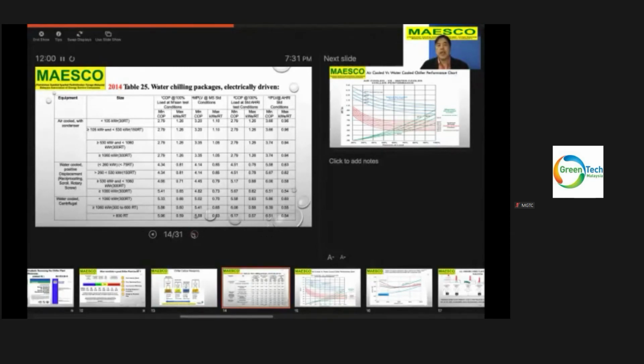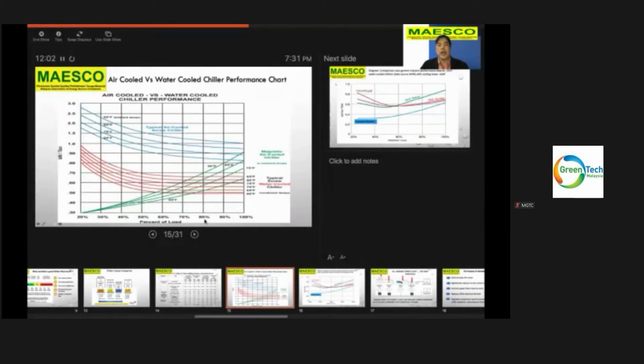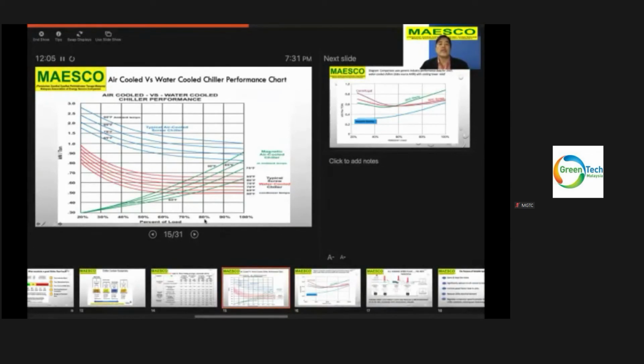Now let's look at the other one, air-cooled versus water-cooled chiller performance charts. You must know all these charts, because if you select the wrong chiller for a wrong application, it's like a baby. The life cycle of the chiller is roughly 20 years. And if you select the wrong chillers, you are stuck with the chillers for the next 20 years. So always be aware of all these charts. These charts are taken from ASHRAE.